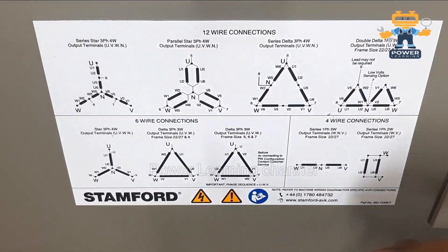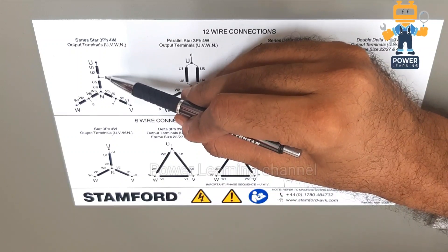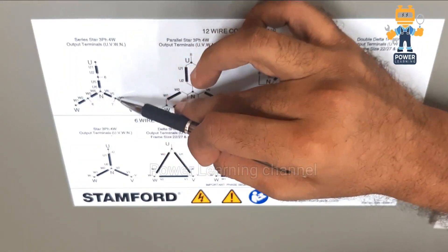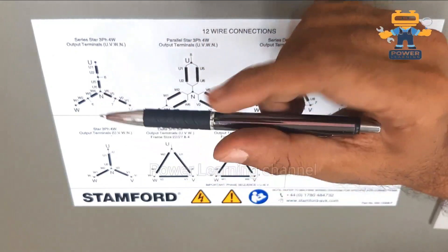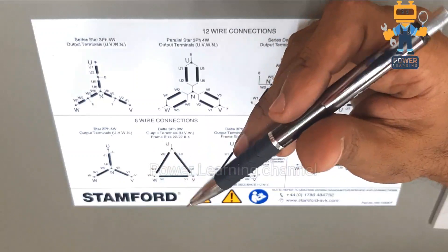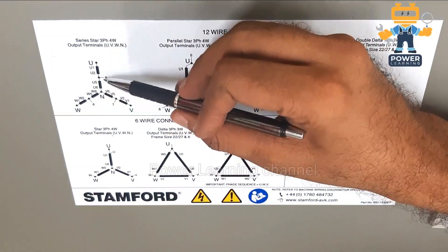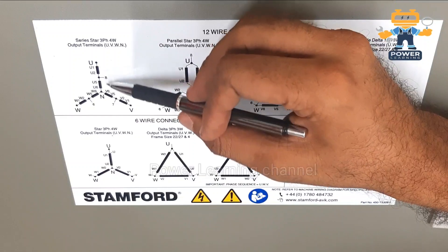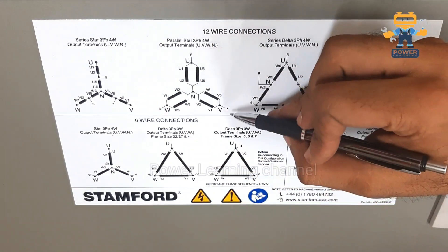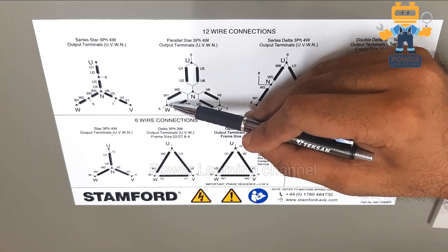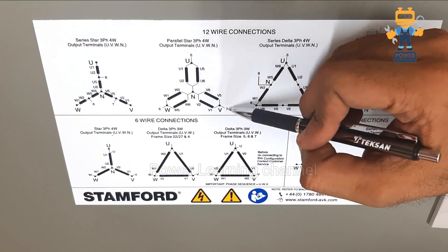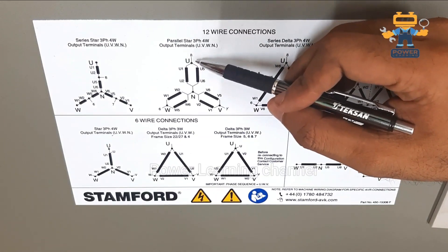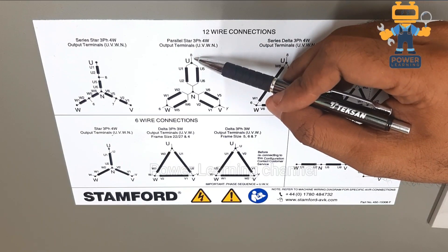For the AVR wiring connection, we have three sensing wires: 6, 7, and 8. If you are using a three-phase AVR, you must use all three wires — 6, 7, and 8. You connect the two control cables of the AVR to the alternator, and the sensing wire goes on the main terminal. If you are using a single-phase 220V system, you take only two wires: 8 and 7.